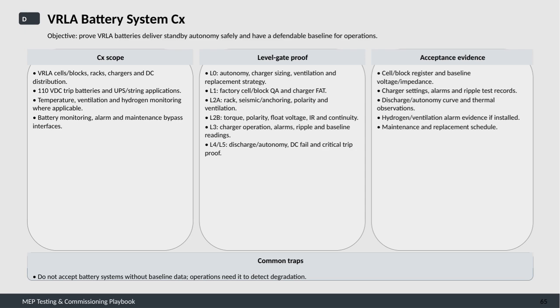The commissioning process is broken down into several stages. Initially, autonomy, charger sizing, ventilation, and replacement strategy are confirmed at level 0. Factory quality assurance of cells and blocks, along with charger factory acceptance testing, happens at level 1. Level 2 is split into 2 parts.